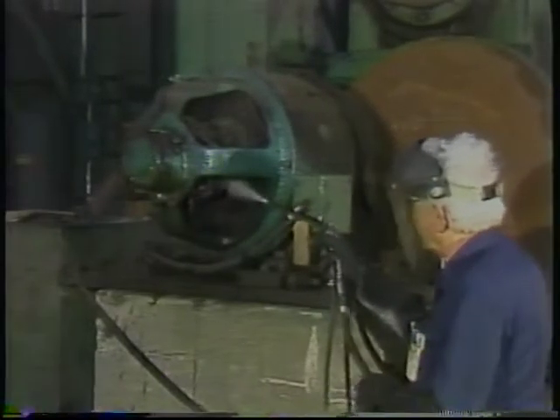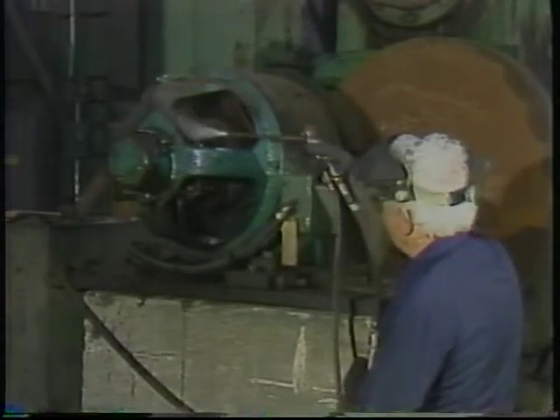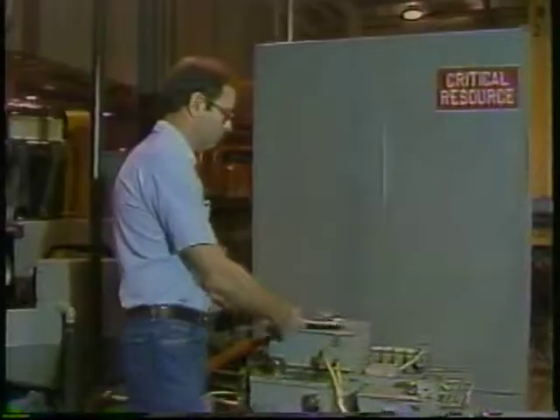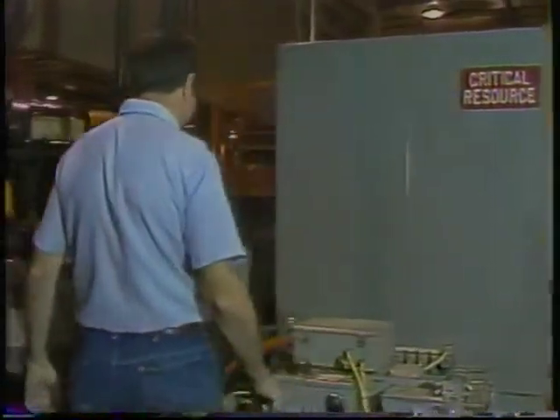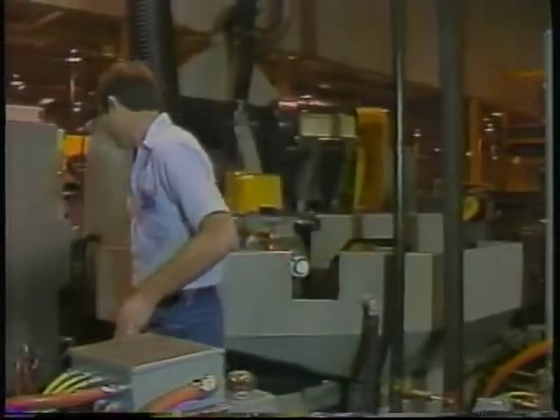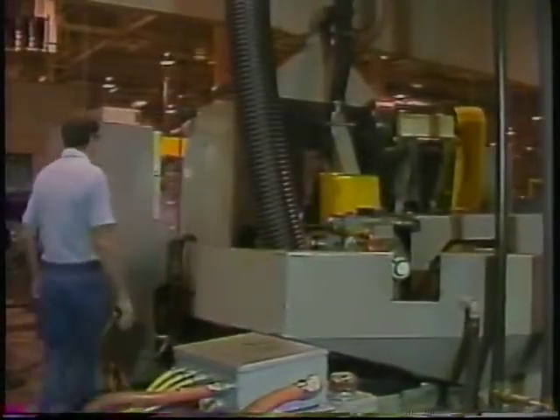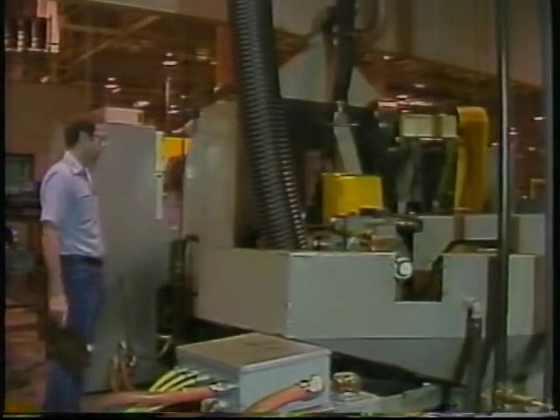Whatever you decide the root cause is, take steps to correct it. Perhaps lubrication or other maintenance schedules need to be modified. Possibly equipment alteration or readjustment overloaded the motor. The motor may not have been the right one for the job in the first place. Getting to the root cause can save you a lot of trouble in the future.